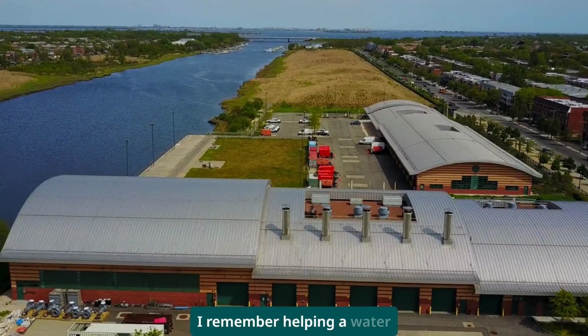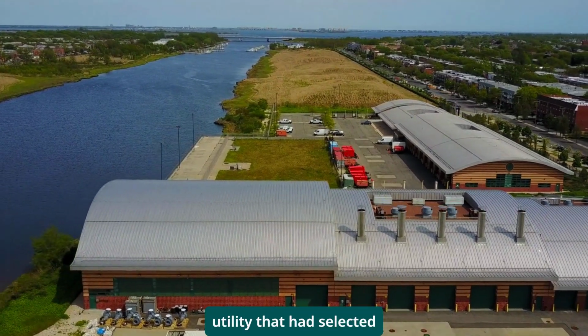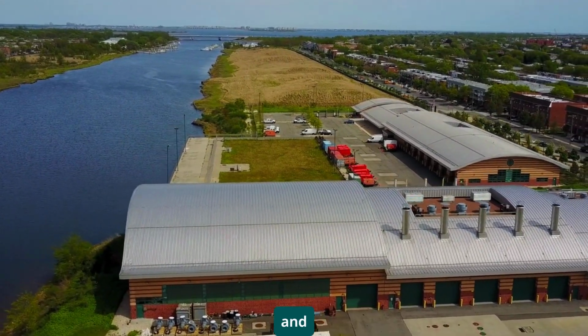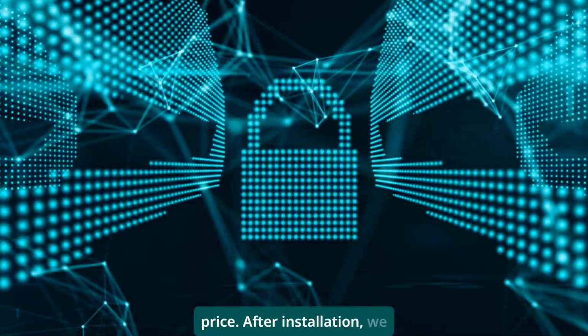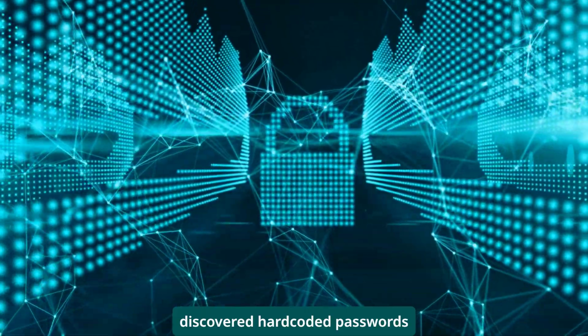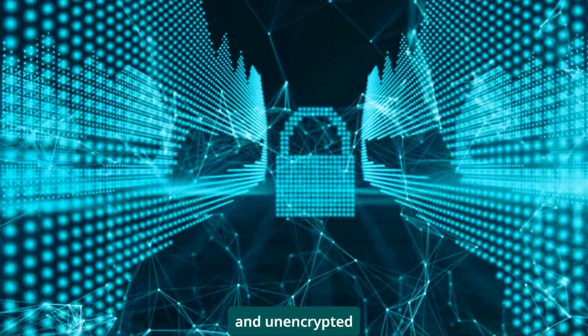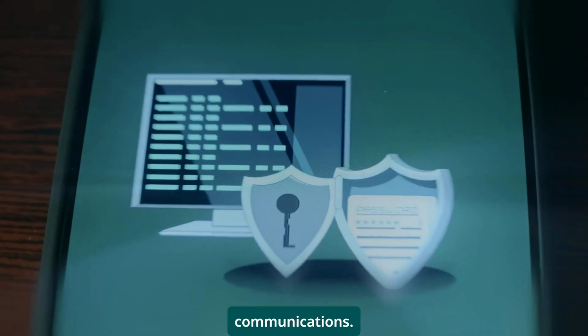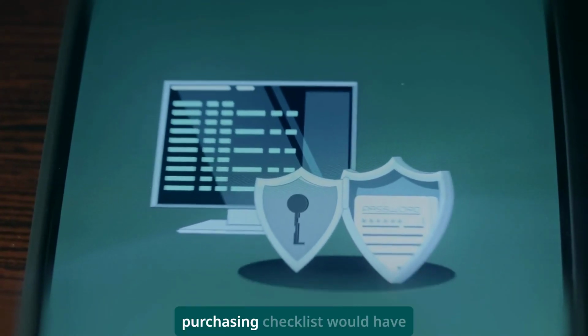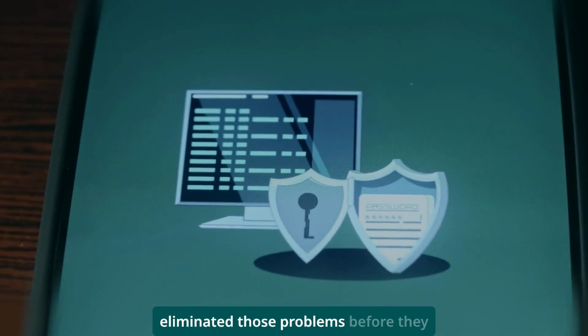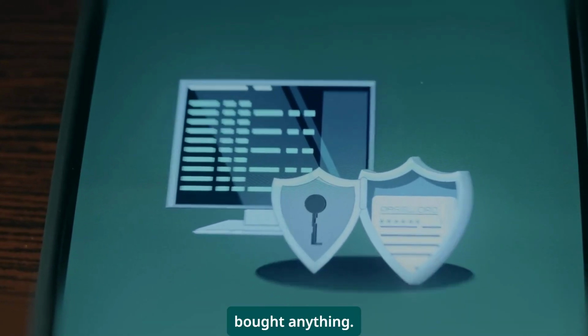I remember helping a water utility that had selected systems based only on features and price. After installation, we discovered hard-coded passwords they couldn't change and unencrypted communications. Using 4.2 as a purchasing checklist would have eliminated those problems before they bought anything.